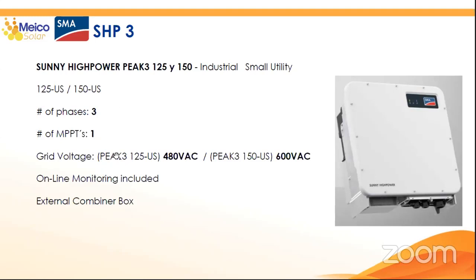Okay, so the 125 kilowatt has an exit of 480 volts. The 150 kilowatt has an exit of 600 volts. So this is very important, because when you are installing in small utility, you don't care about the voltage. Even working with higher voltage is better. So working at 600 volts reduces the cost of the BOS, and you will also have to step up to connect to 13.2 kilovolts or 32 kilovolts, I don't know, depending. So you don't have a problem working at higher voltage.